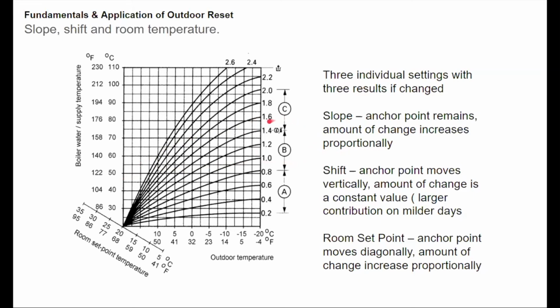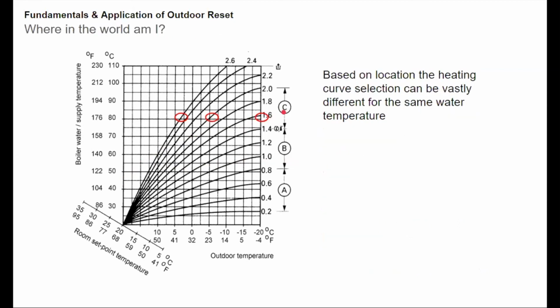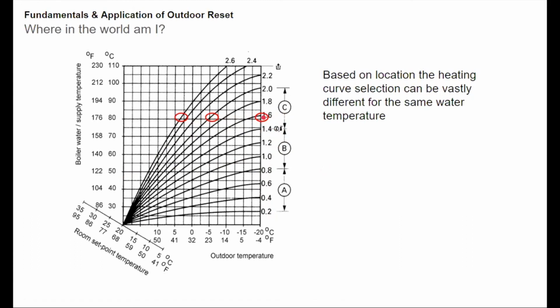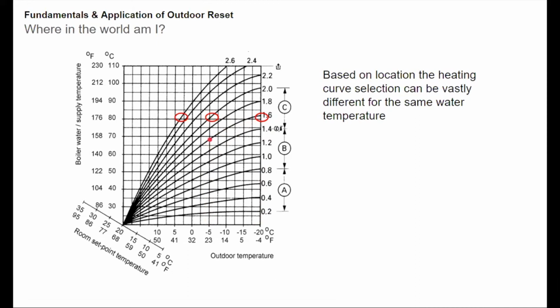Now, one thing about the slope and the curve: I keep on talking about these numbers, A, B, and C, under certain conditions. So for instance, I'm always saying if I need 180-degree water, I'm at about 1.6. Thing to remember with these curves, it comes up every once in a while, is the curve is also location specific. So a 1.6 curve does give you 180-degree water temperature when you're somewhere around a 0 to -4-degree day. But if my design day is only 23 degrees and I need 180-degree water, that 1.6 curve isn't going to get me anywhere near it.